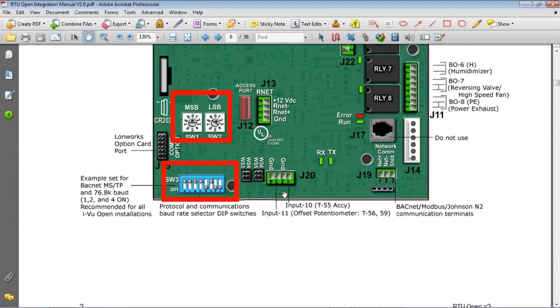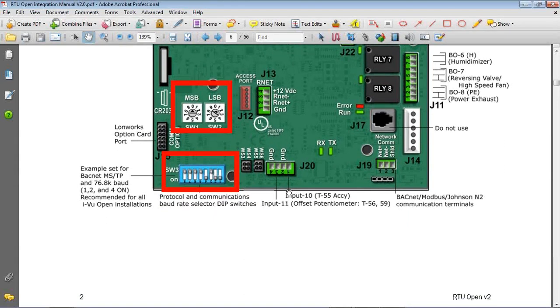And then the other part is this DIP switch down here, which allows you to select the baud rate. It also allows you to select what type of communication you're doing, if you're doing BACnet or Modbus or N2. In this integration guide, there's a manual that tells you which DIP switches need to be where. For instance, we're looking at this example for BACnet MSTP and a baud rate of 76.8. You need 1 and 2 to be switched on and 4 to be on.